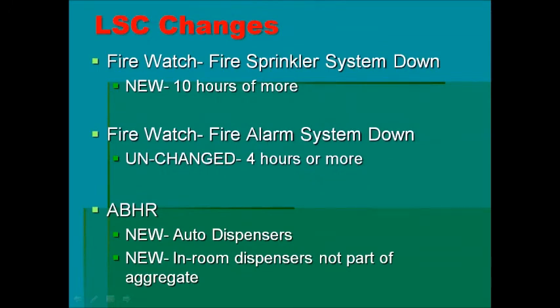So, as we start to wind down, let's go through some of the main things. There's a new requirement for fire watch, and you need to make sure your fire watch policy, procedure, logs, and other collateral reflect this. You have to understand that the code and CMS say you have to trigger a fire watch unless your sprinkler system is compromised for 10 hours or more. Previously it was 4 hours or more, and many fire watch policies I see still say 4 hours, but surveyors want to see your policy upgraded to the new requirement of 10 hours or more. If your system goes down because of a leak, a problem, a break, or no water pressure for more than 10 hours, then you have to trigger a fire watch.